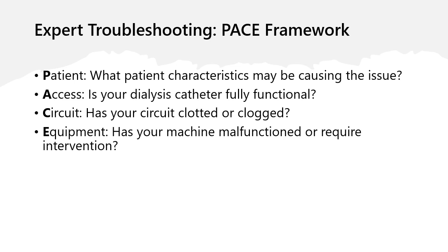can be done as that filter has reached the end of its natural useful lifespan. However, if the filter has clotted, and the delta P, or pressure drop, has been rising steadily, this may be an indication for citrate if the patient is appropriate for it, or if they've been on systemic anticoagulation, it is still appropriate to add regional anticoagulation through citrate, and that's something that some providers may feel uncomfortable with at first due to lack of experience. However, it is a fully valid method of keeping the circuit functional.